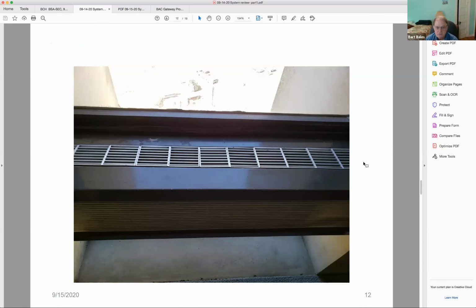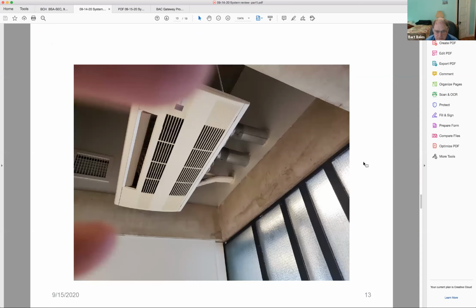This is just a typical perimeter unit. This blows air out and has a heating and cooling coil in there. Next. Another delivery terminal unit, typical unit. This is the kind of unit that we might be replacing with a heat pump head and with condenser capacity somewhere else, which might be borehole related, or it might be condensers located on the roof.